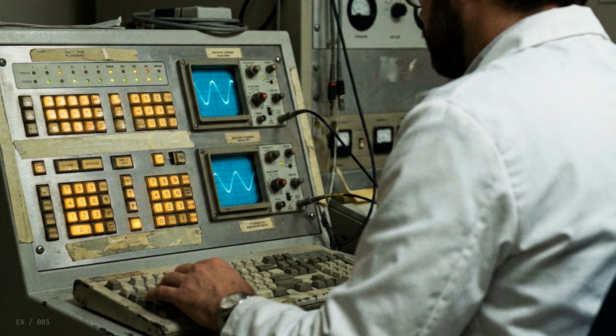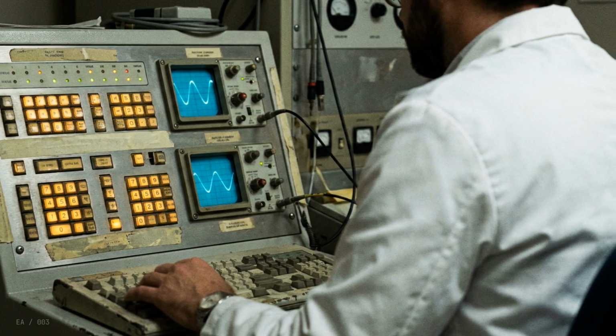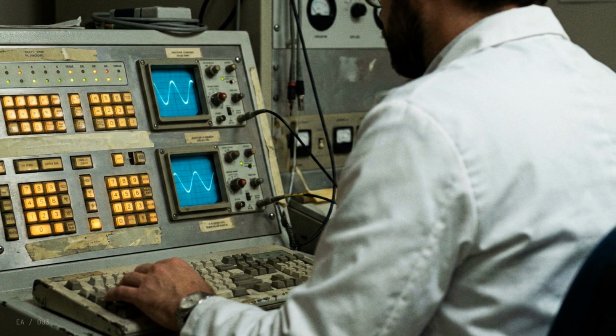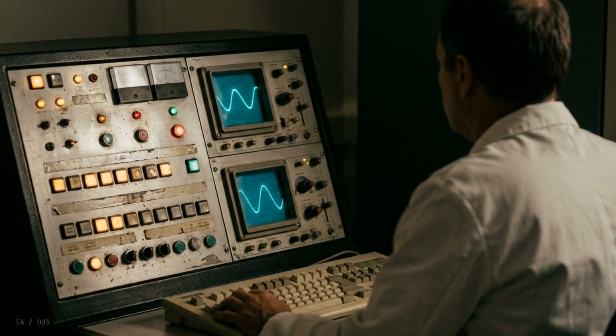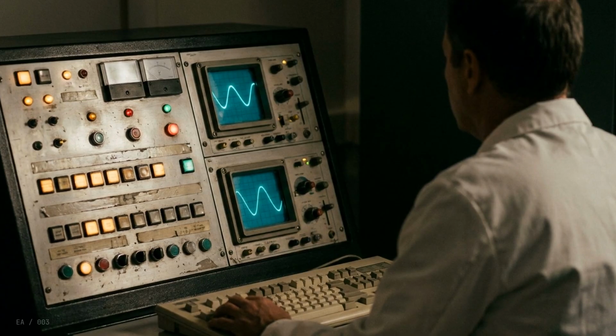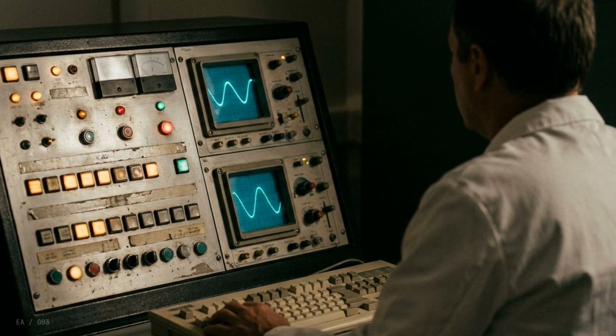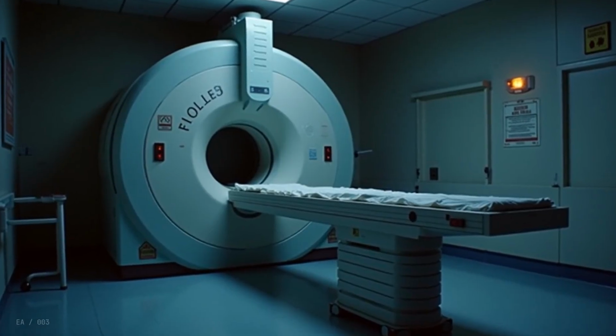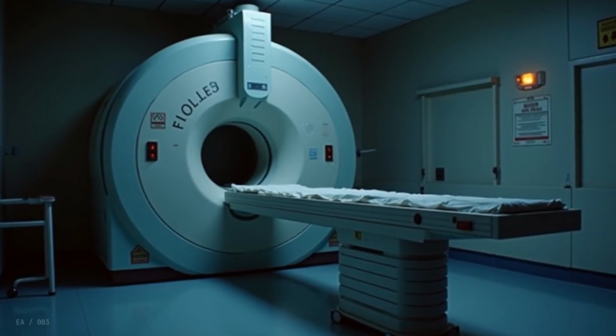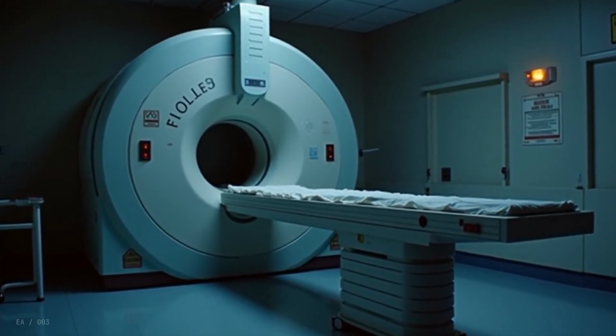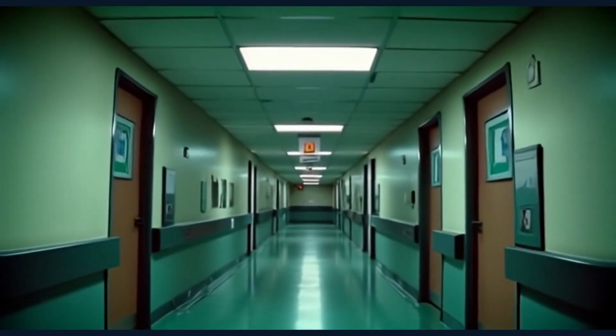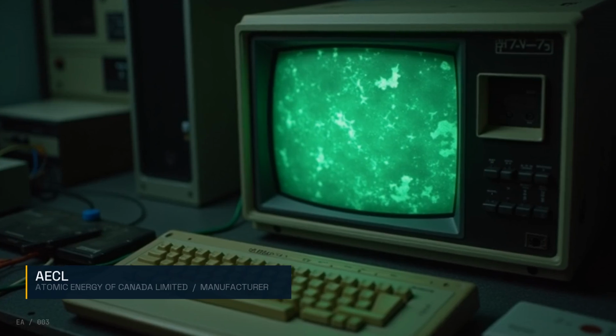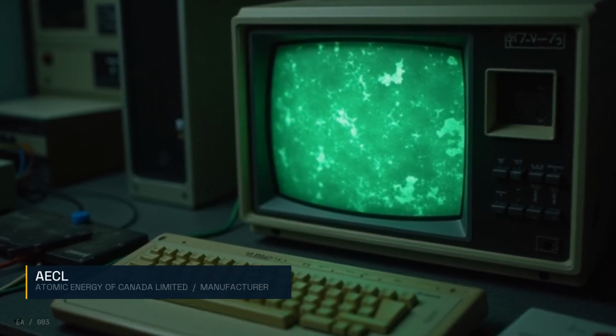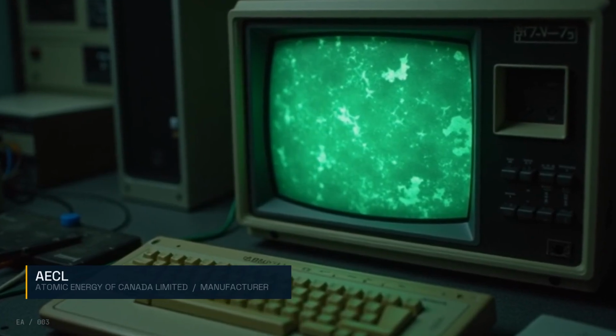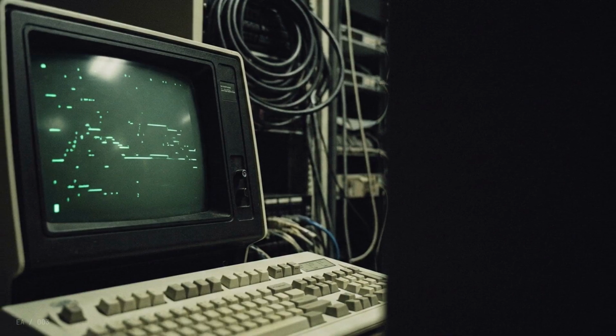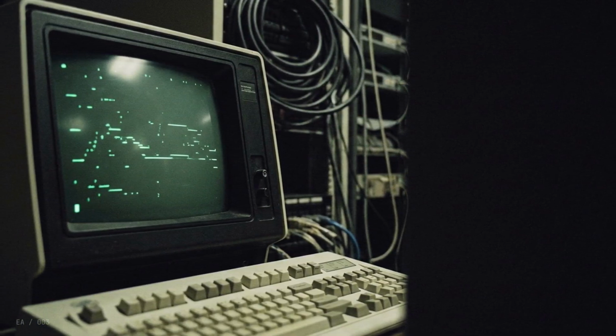The Therac-25 had 2 predecessors. The Therac-6, built in 1972. The Therac-20 in 1976. Both used the same dual-mode design. Both had 3 independent hardware interlocks, mechanical switches and micro-switches that confirmed the spreader plate's actual physical position before the beam was allowed to fire. In 1982, when AECL released the Therac-25, they removed all 3. They removed them because the software, they argued, already verified the spreader plate's position. A hardware interlock was redundant. It cost roughly $3,000 per unit to manufacture.